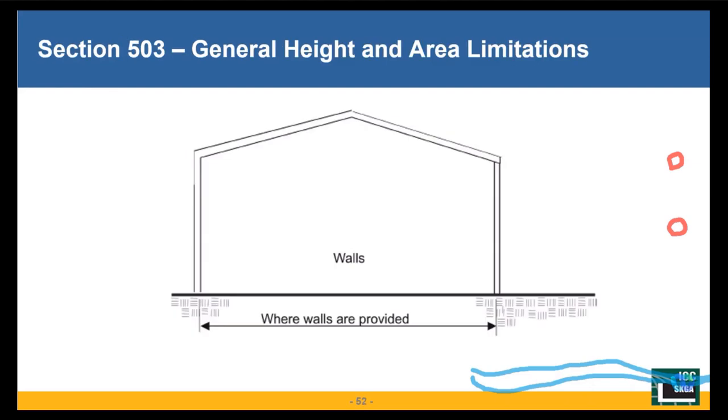But before we do, we have to figure out, and this has been debatable for many fire and building officials, and most people overlook it, what area you're looking at. The area you're looking at of a building or structure is only the area per story. And that area is the pure number that you pick from Table 506.2. And it's the area surrounded by the exterior walls. So it's from the inside of the wall to the inside of the other wall.